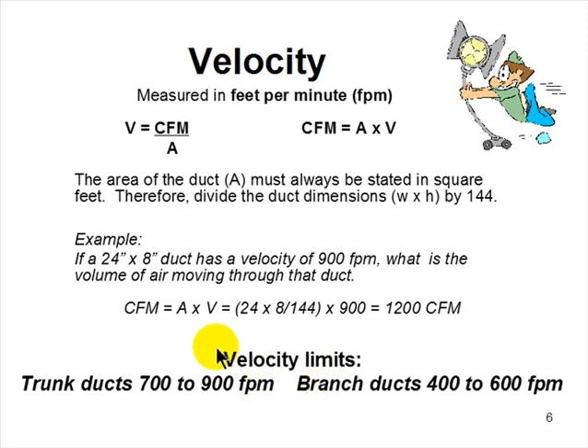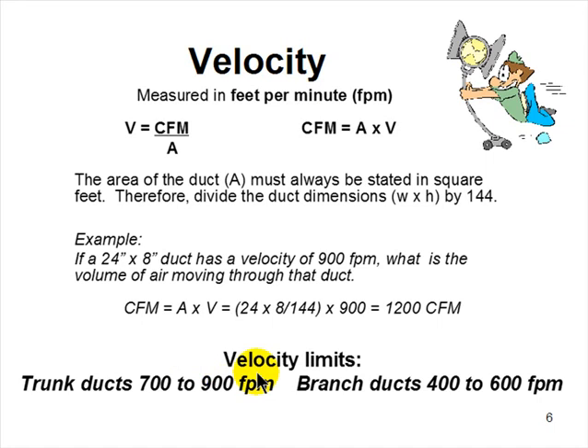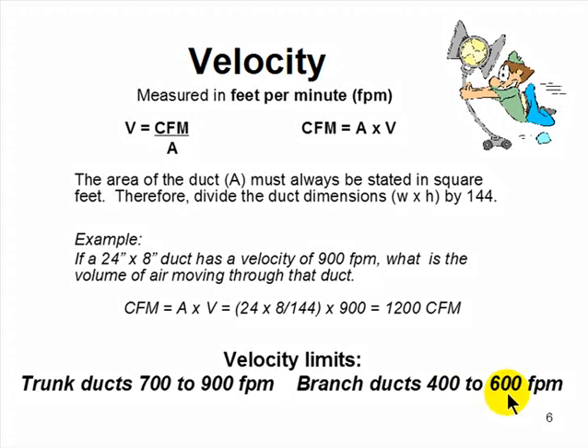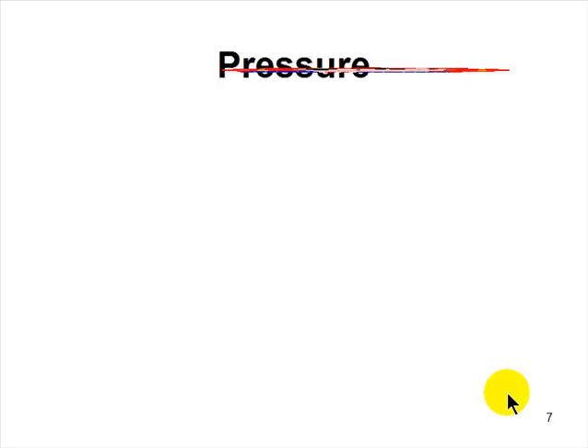Velocity limits on ductwork: trunk ducts — main rectangular or round trunk ducts — should be kept between 700 and 900 feet per minute for a good system. At 700 FPM you'll have decent projection out of the registers into the room. Above 900 FPM you'll start to get noise from moving the air. Branch ducts should be kept between 400 and 600 FPM. Below 400 FPM, you won't feel the air coming out of the register. Above 600 FPM, you'll get noise at the register or grill.